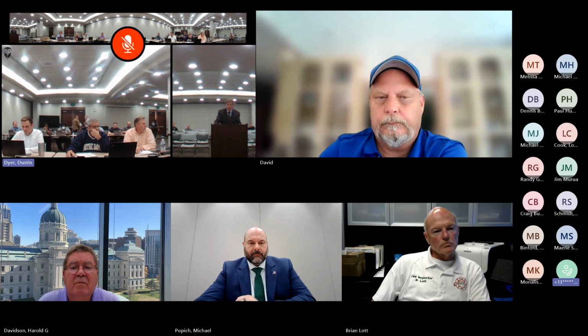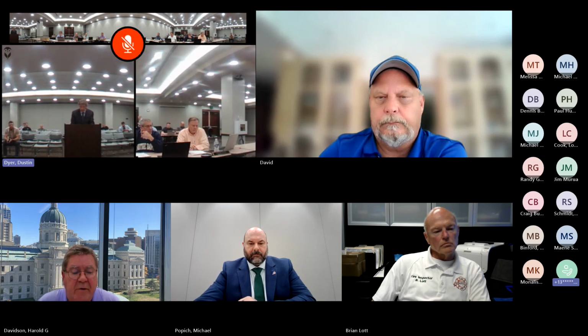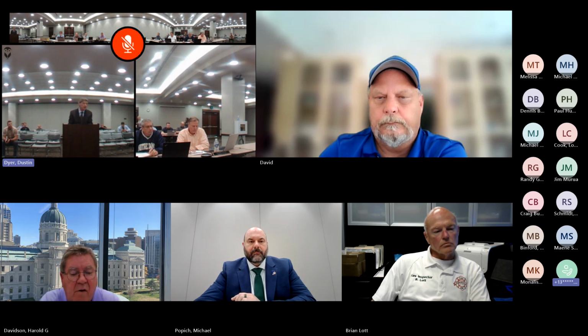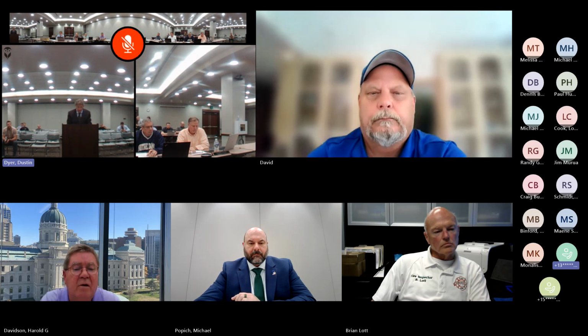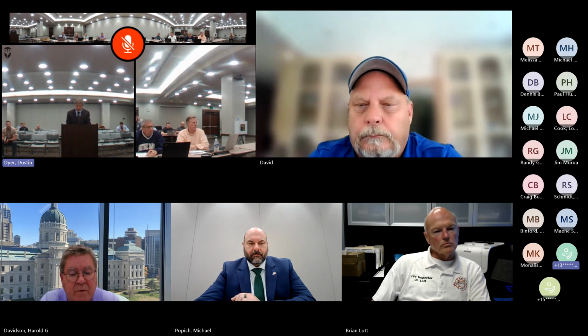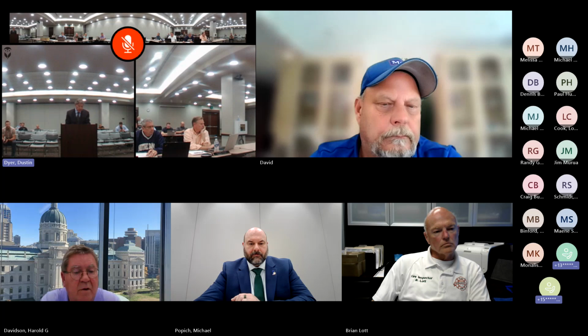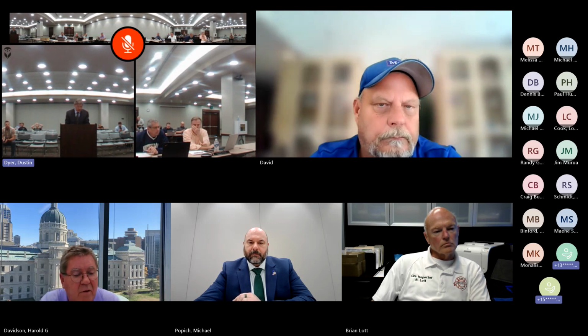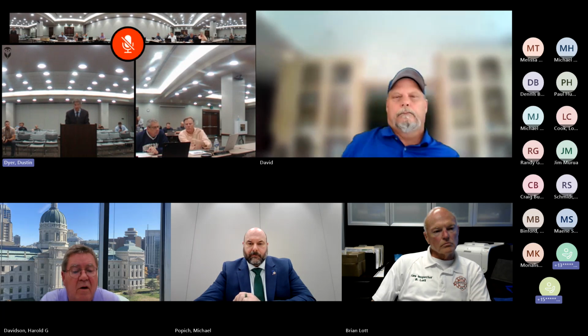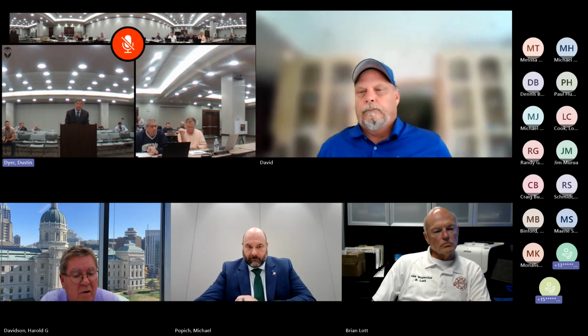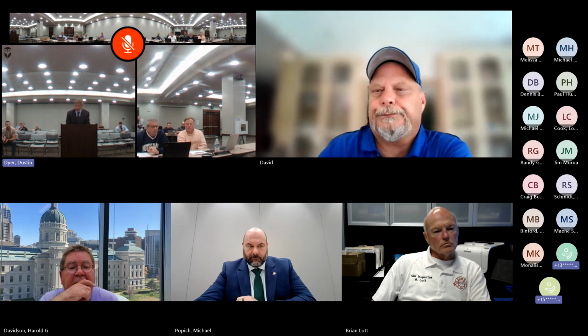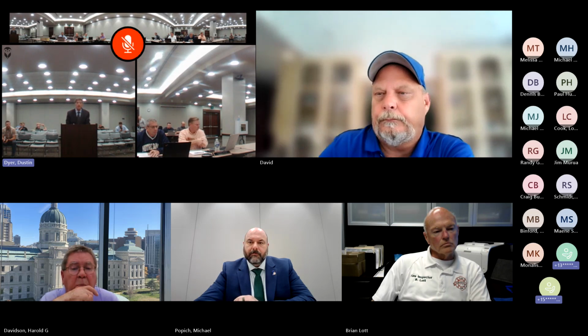My understanding is that I had Christina look at this and give an opinion about the temperature issue at least. At that time we were still a little confused about how many standard response versus quick response sprinklers there were, but we feel that the 155-degree heads are fine—they're sufficiently above the ambient temperature for what we would expect. My understanding is that the fire department is not opposed to maintaining 155-degree heads, but they are opposed to the use of any standard response sprinklers.